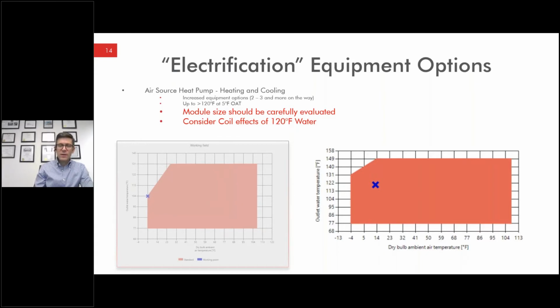You can design around it, but the other thing is, you see in that image, the pink or red is the operating range, and we're right on the edge of the operating range. As an engineer, you probably don't like to be at that selection point. It wasn't an ideal condition. On the flip side, the right-hand image is a selection we received on a project we were designing last year, showing that between -4 and up, 120 degree water is very achievable. This is a much more comfortable selection for us and something we've been working towards, and it's really what we've been seeing as the sweet spot for our selections.